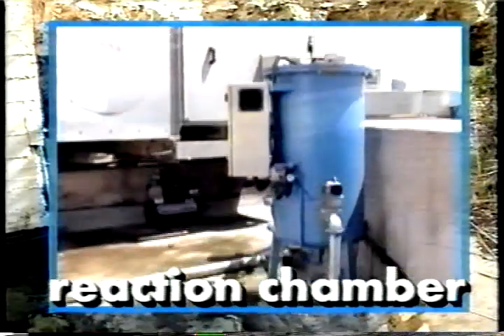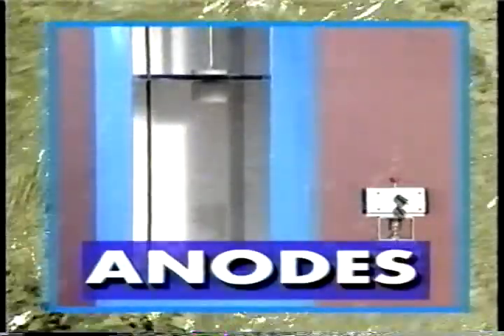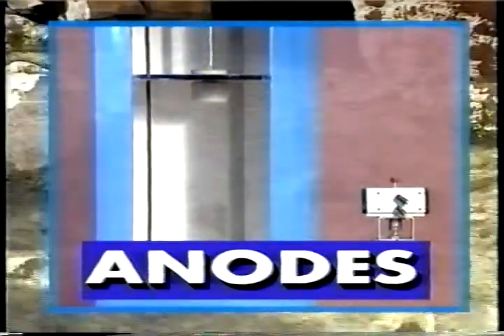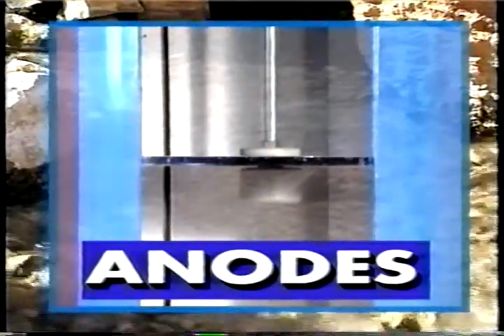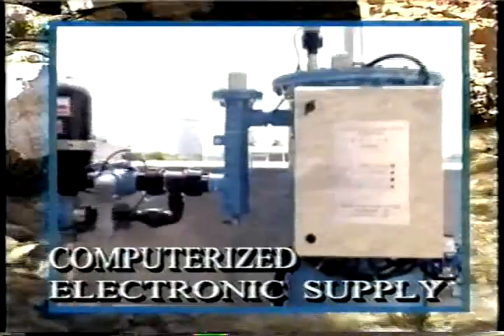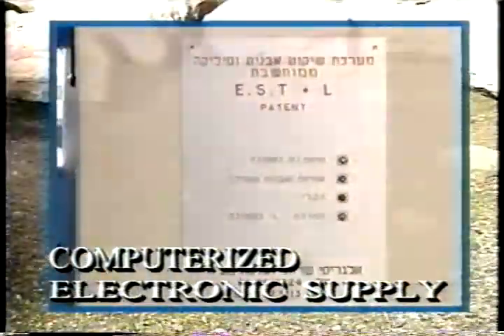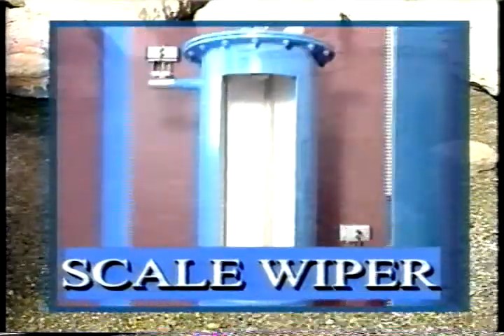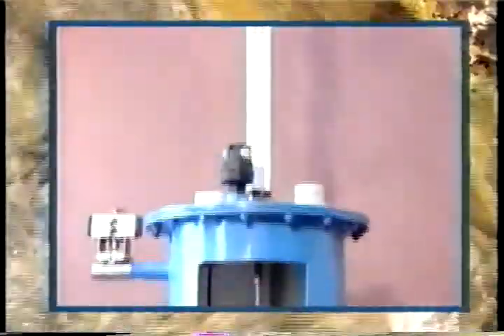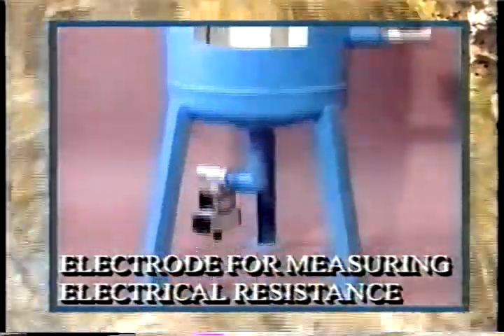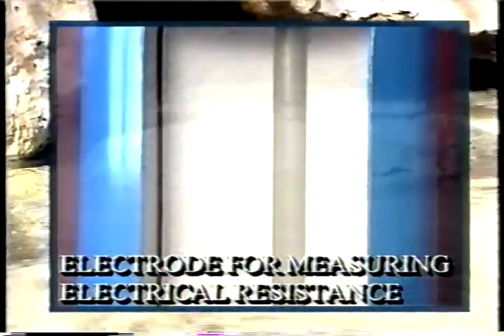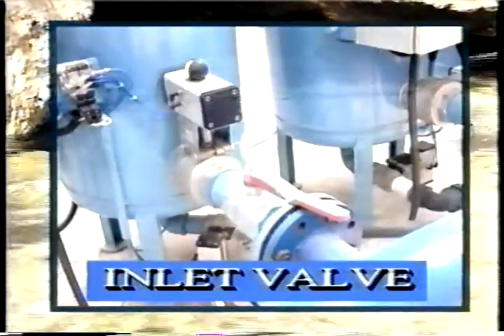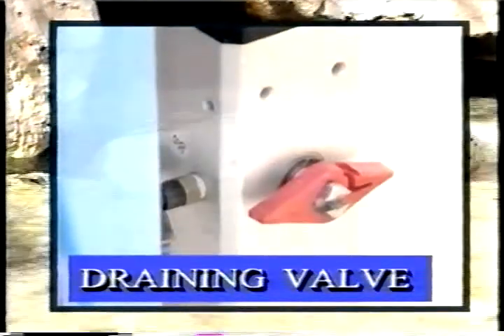The EST plus L system is composed of a separate reaction chamber, anodes specially developed for the electrolytic process that do not dissolve in the water, do not contaminate the water, and function for many years without needing replacement. Computerized electronic supply for continuous control and monitoring of the electrolytic process and system operation. Piston-actuated scale wiper removes scale from the chamber walls. Electrode for measuring electrical resistance of the water and softening scale by electric shock. Ball valve at the inlet to the chamber, and a drain ball valve at its bottom.